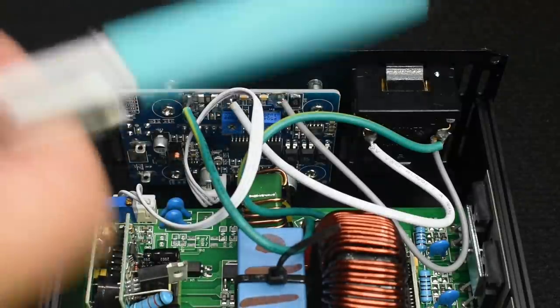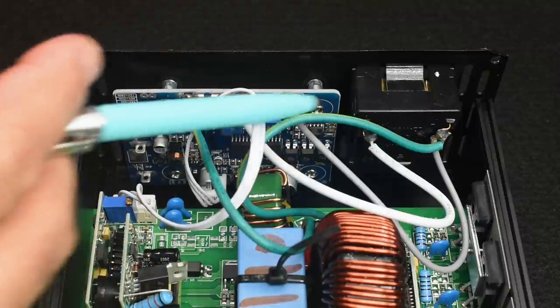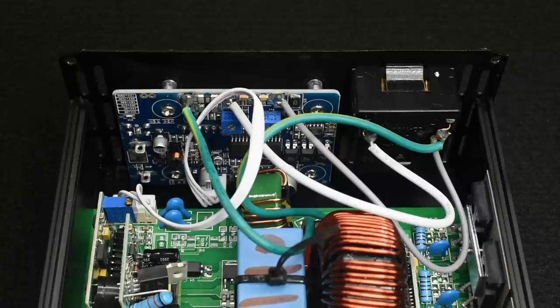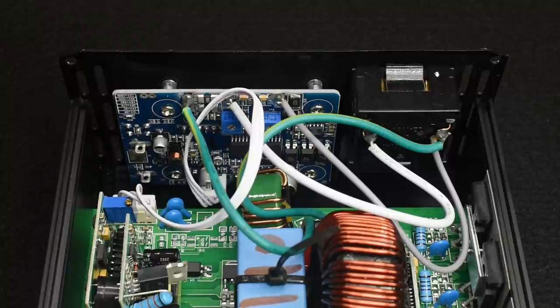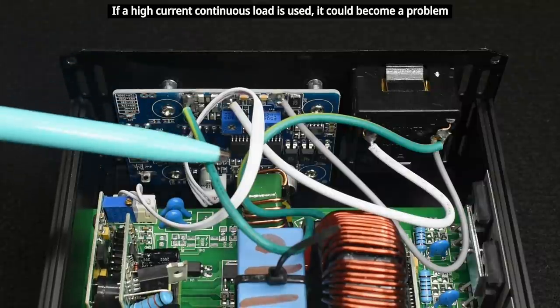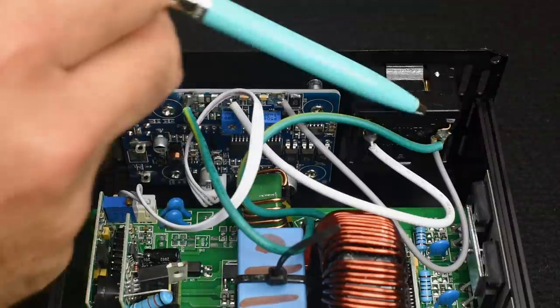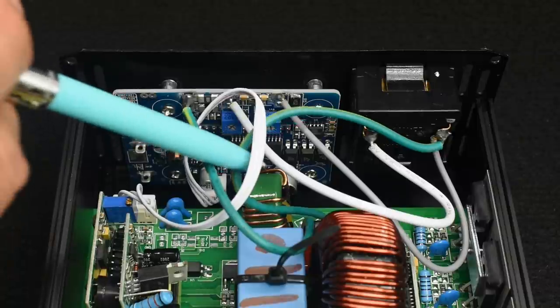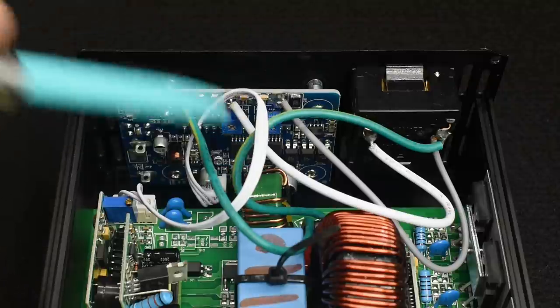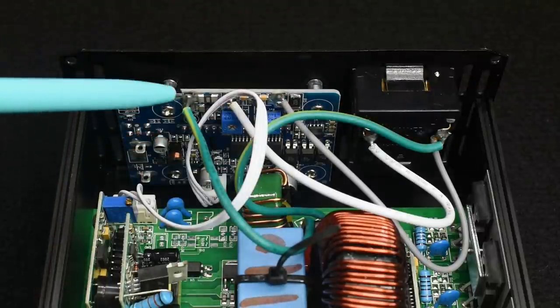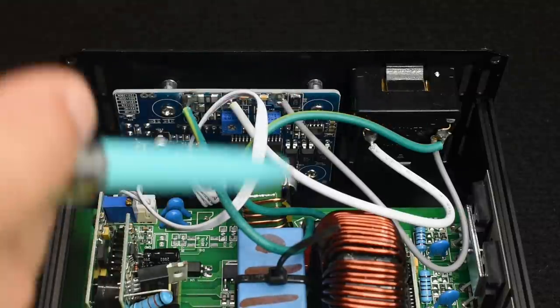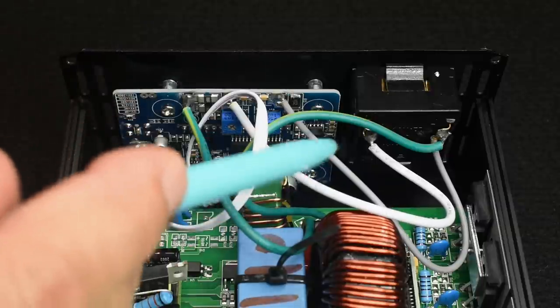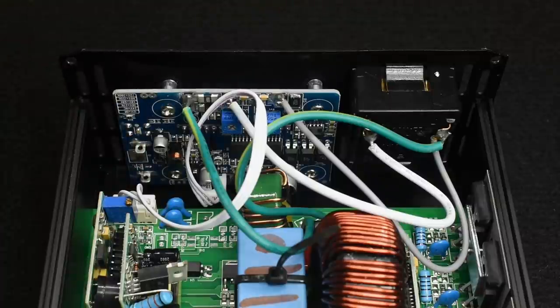Now the wire right here looks a little thin to be carrying the current for a 2,000 watt load continuously. It's a number 18. Number 18 really can only handle about 10 or 12 amps. When you get higher than that, you're going to have too much resistance in that wire, and the wire is going to begin to heat up. If you decide to make this a little thicker, which is probably a good idea, I would go with number 14. Just swap out the green wire from the board to here, and the green wire from the board to this point. You want to change this out as well because it goes from the board to the receptacle.